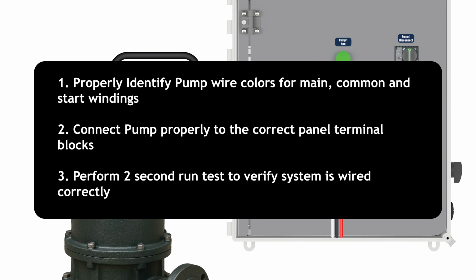In conclusion, properly identify the pump's color scheme associated with the common, main, and start windings, and connect to the corresponding properly labeled common, main, and start winding in the control panel. Perform 2-second run tests to verify the system is wired correctly.